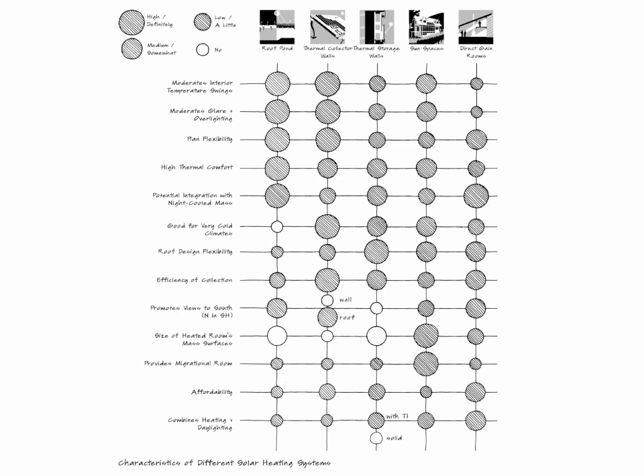In the passive solar building bundle, you'll find a chart showing characteristics of different solar heating systems. Across the top: direct gain rooms, sunspaces, thermal storage walls, and thermal collector walls. There's also one more system we haven't talked about yet — the roof pond. Roof pond means the thermal storage is on the ceiling in bags of water; we move insulation to cover or uncover it so it can either get sun or be insulated from losing heat. Transfer is by radiation through the ceiling. It works only at low-latitude climates in winter — it doesn't work well at high latitude because of the sun angle.